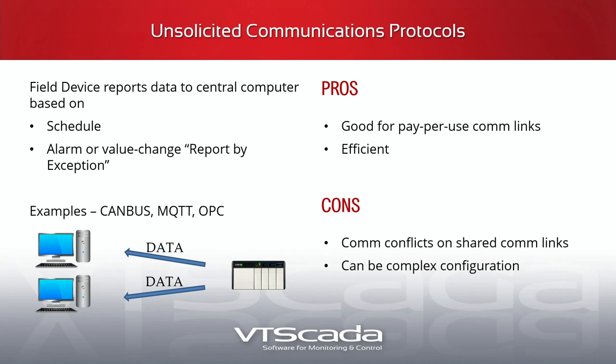A con with unsolicited on serial comm links: if multiple devices decide to talk at the same time, you hear garbled messages. Unless each device is smart enough to detect someone else is talking and wait, you have a nightmare. We've had systems using DNP3 — a very common, capable protocol — on serial with hundreds of RTUs trying to talk simultaneously with no information getting through. You have to set back-off rates so each tries at slightly different intervals, which is terrible to organize.